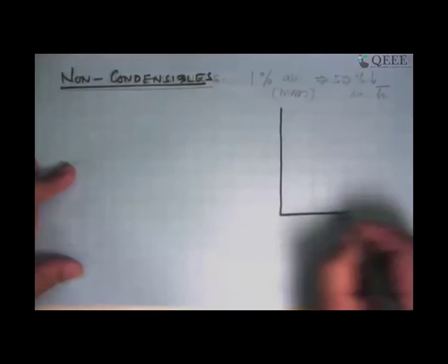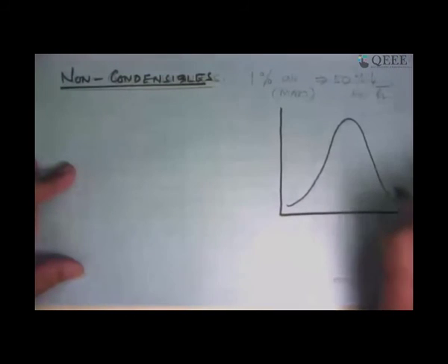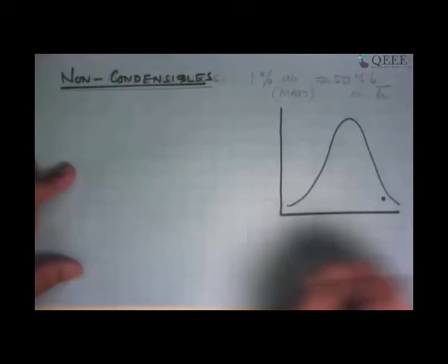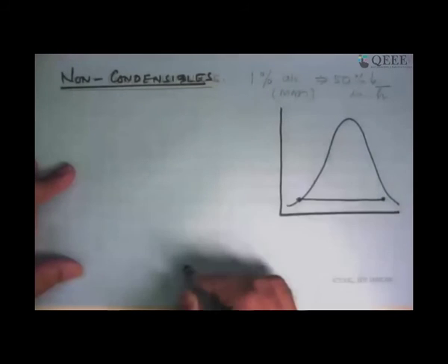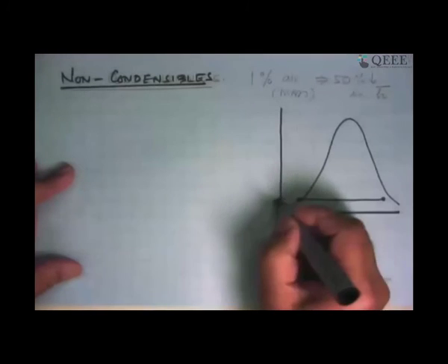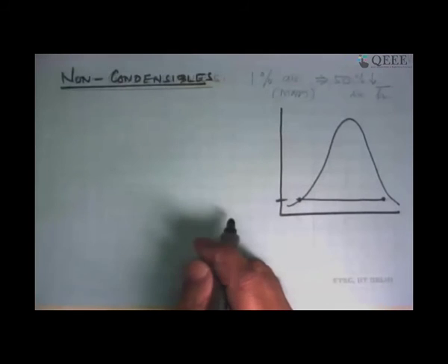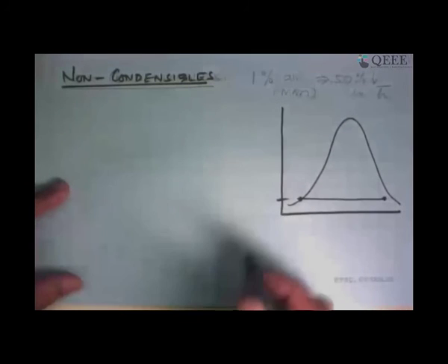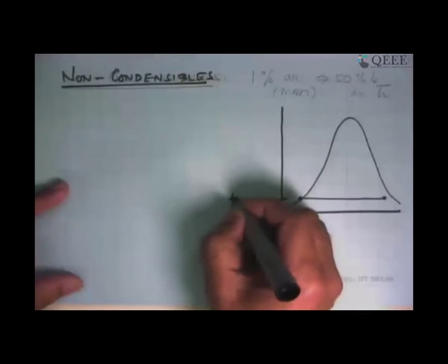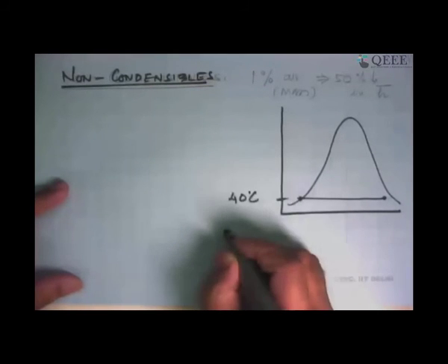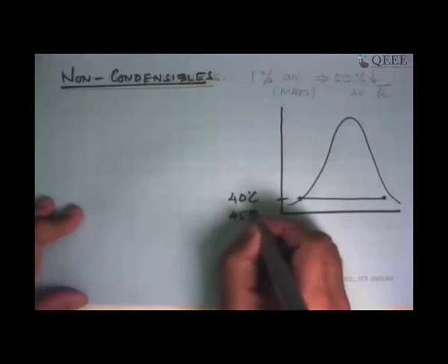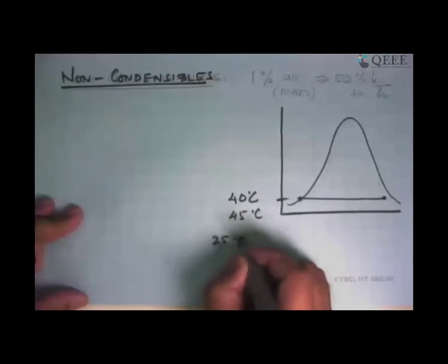And why is this important? Let's take the example of a power plant condenser, and if you look at the TS diagram and everything else that we do, this is the thing. The inlet condition to the condenser is this, and we want to condense it into this. And the temperature at which we want to do it is the lowest possible temperature that we have, which is the ambient water temperature or the air temperature. That is where we are dumping the heat. So typical condensation temperatures will be of the order of 40-45 degrees Celsius, because the water could be like 25 to 30-35 degrees Celsius.